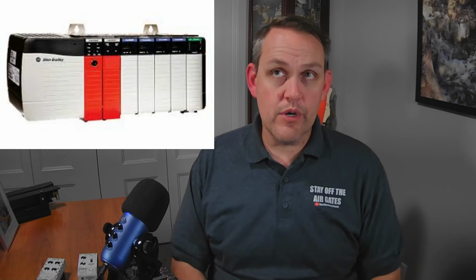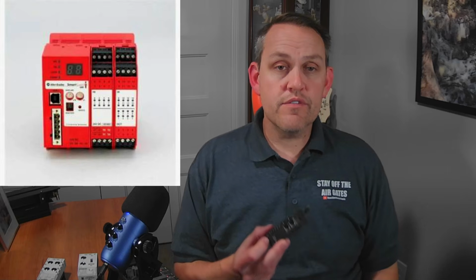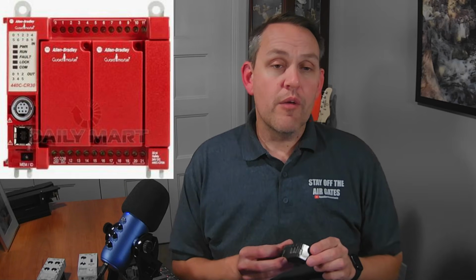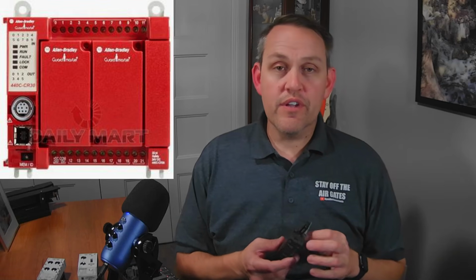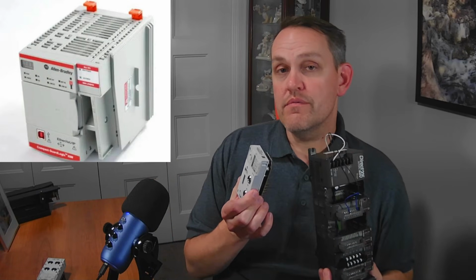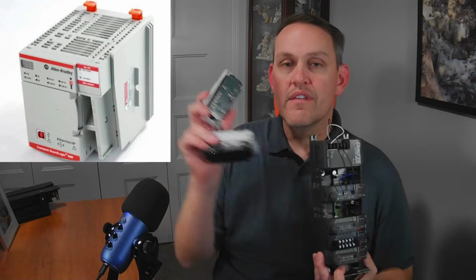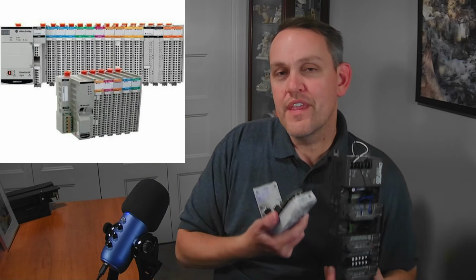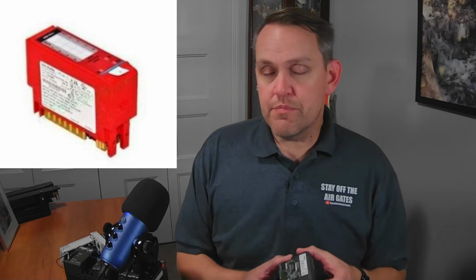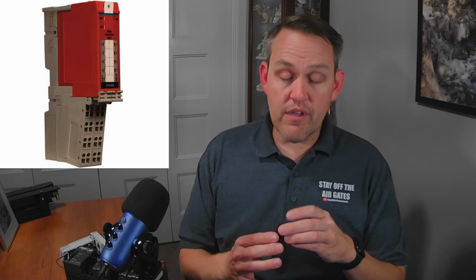Allen Bradley makes the most of the safety PLCs out there, although if you go to any manufacturer out there, they have PLCs that are rated for safety. They're a very special rating. Typically they're a different color. There's lots of indicators that it is something special. But the interesting thing about a safety processor is that it does the exact same thing that the 2 processors did, but it uses a 3rd processor now. Everything is built into it. Even the I/O is different. It's very interesting. Now, to be fair, it's one of the systems I also have the least experience with. So if I get stuff wrong, you'll have to apologize now.